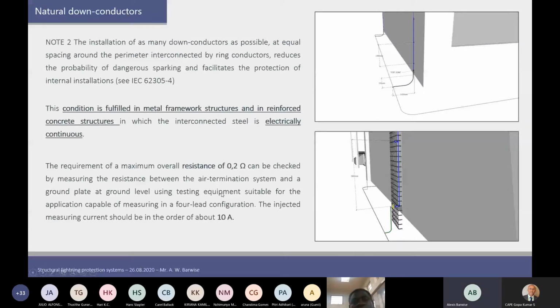Here we see the use of two different types of down conductors. On the top right, we see a purposefully built and installed, right? So there's an external down conductor running down the side of the building. And here we see a reinforced concrete column, which has multiple steel paths going from the top to the bottom. So here we start seeing again the introduction of natural elements, such as reinforced concrete columns or I-beam steel columns coming down. And we read again from the standard that the installation of as many down conductors as possible at equal spacing, right, reduces the probability of dangerous sparking and facilitates the internal installation protections in part 4, surge protection, which Professor Gomez will cover later.